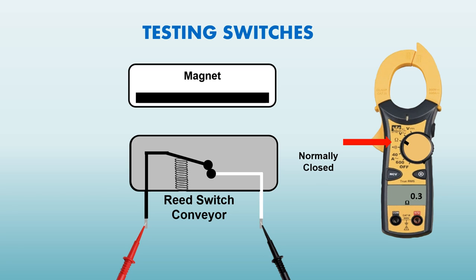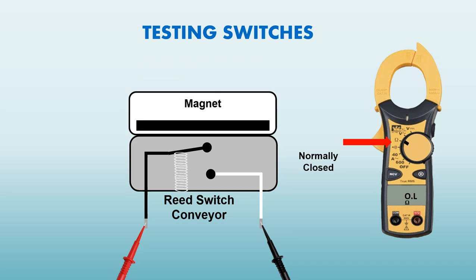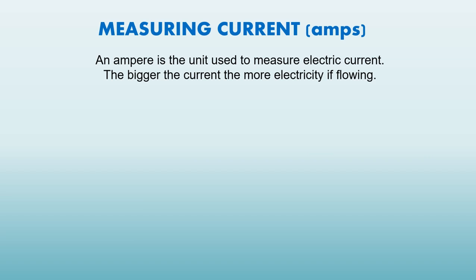disconnect the reed switch from the wiring on the system. Again, always verify there is no power to the system. Adjust your voltmeter to read for ohms. Connect your terminals to each end of the reed switch to test for continuity to see if the switch is closed. To verify if the switch is working properly, you can activate the sequence bar to open and close the switch to see if the switch turns on and turns off. This is a very simple way, without removing the switch from the machine, to verify whether it's working or not working for you.